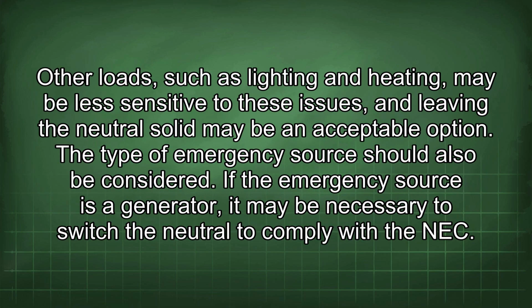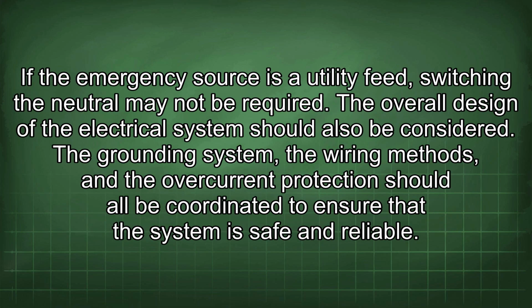Other loads, such as lighting and heating, may be less sensitive to these issues, and leaving the neutral solid may be an acceptable option. The type of emergency source should also be considered. If the emergency source is a generator, it may be necessary to switch the neutral to comply with the NEC. If the emergency source is a utility feed, switching the neutral may not be required.